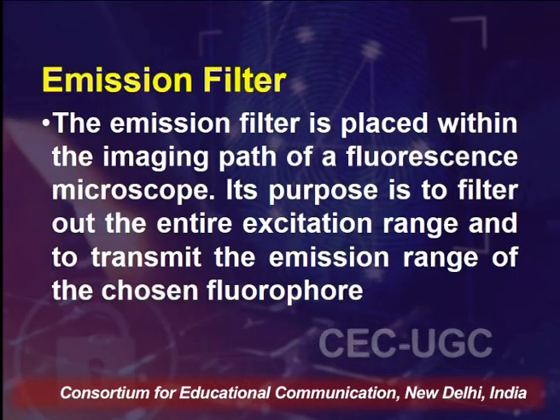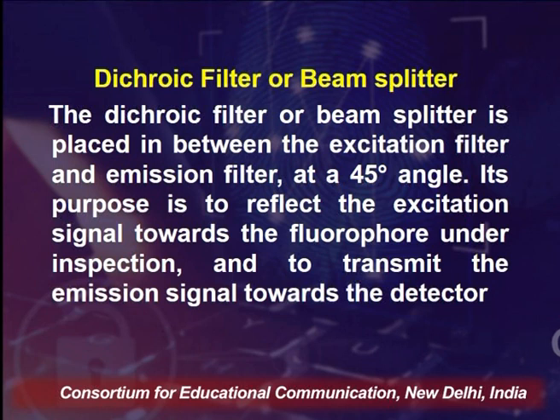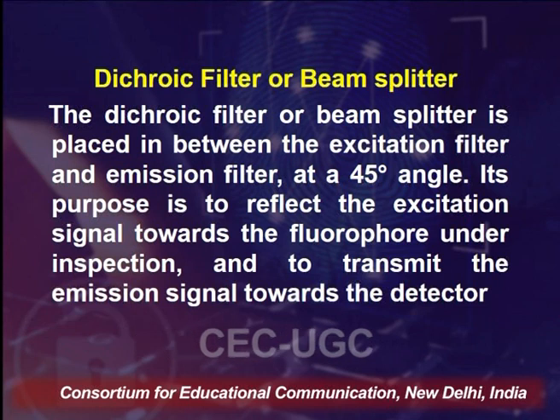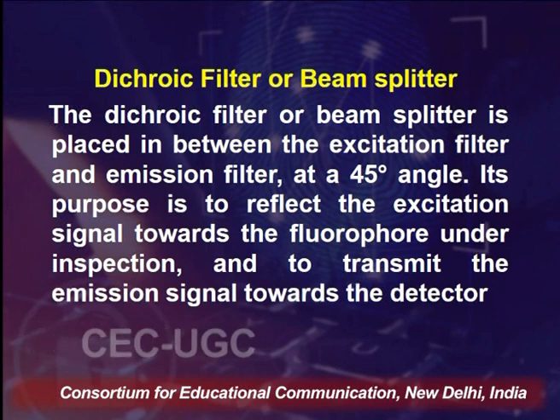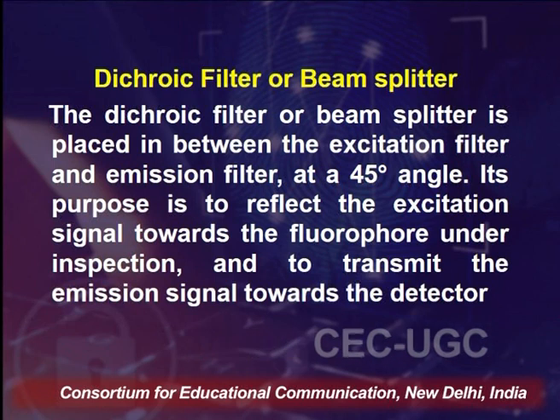The emission filter is placed within the imaging path of a fluorescence microscope. Its purpose is to filter out the entire excitation range and to transmit the emission range of the chosen fluorophore. The dichroic filter or beam splitter is placed between the excitation filter and the emission filter at a 45-degree angle. Its purpose is to reflect the excitation signal towards the fluorophore under inspection and to transmit the emission signal towards the detector.